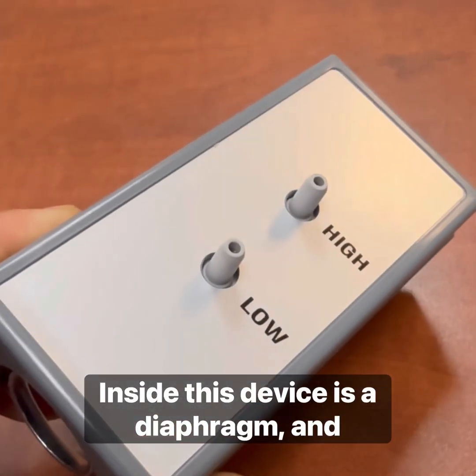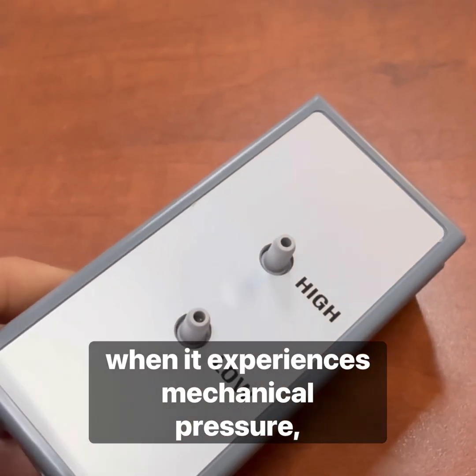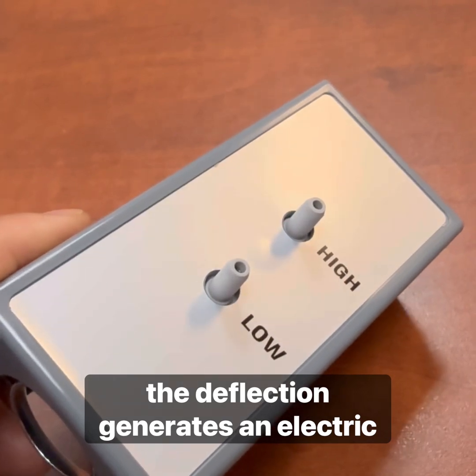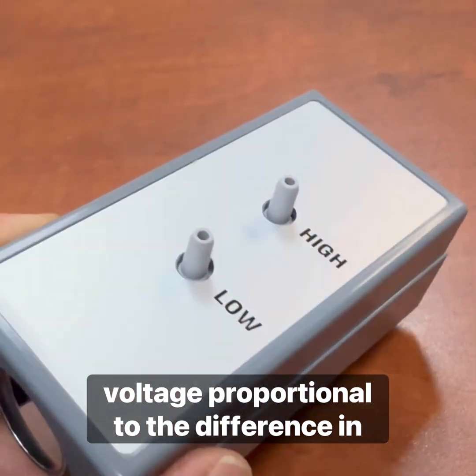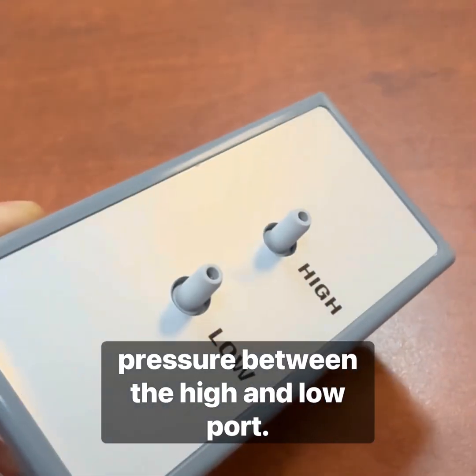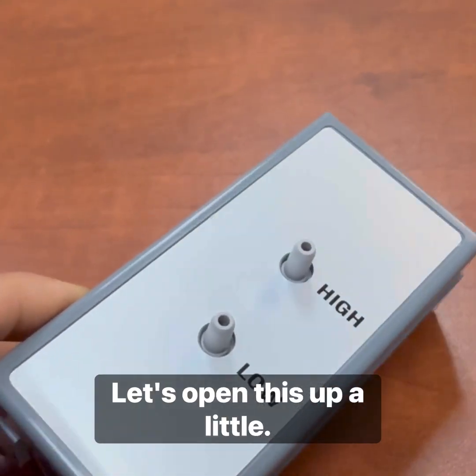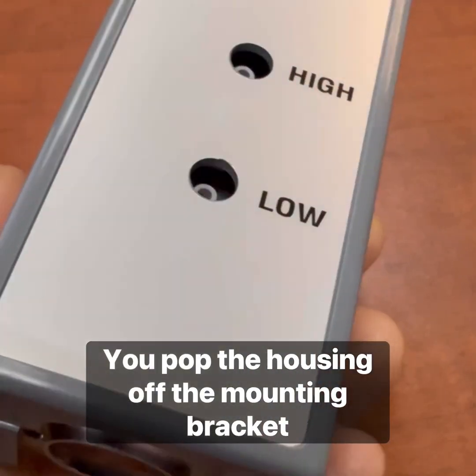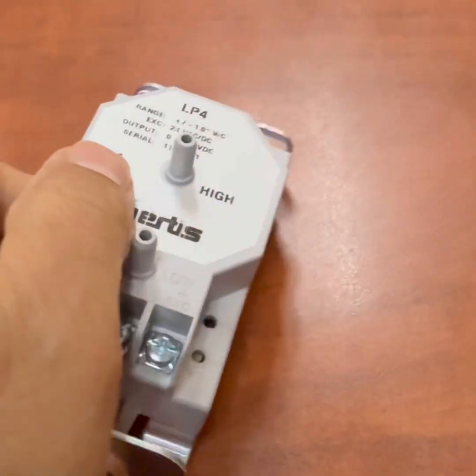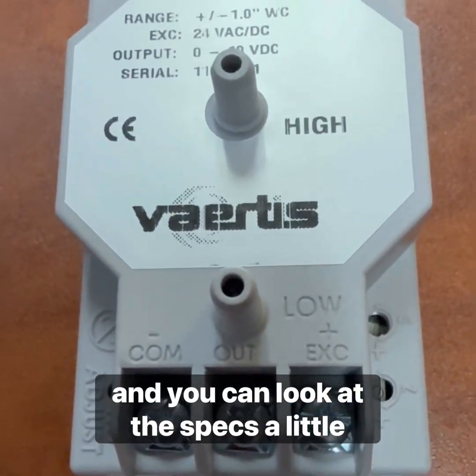Inside this device is a diaphragm, and when it experiences mechanical pressure, the deflection generates an electric voltage proportional to the difference in pressure between the high and low port. Let's open this up a little. You pop the housing off the mounting bracket like this, and you can look at the specs a little bit.